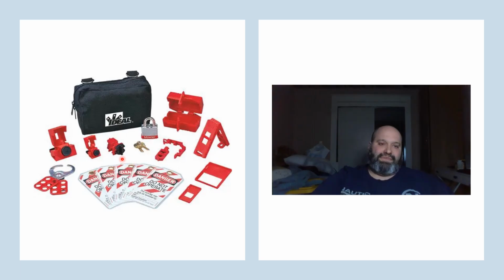You're going to clamp this onto the breaker once it's off, and it's going to inhibit anybody from turning the breaker on. Not only that, but you're going to put one of these on it, and when this claw clamps onto the actual lock, you can't open it because it's clamped on. Then you're going to put a tag saying who you are and what you're doing, fastened to these holes with this padlock.